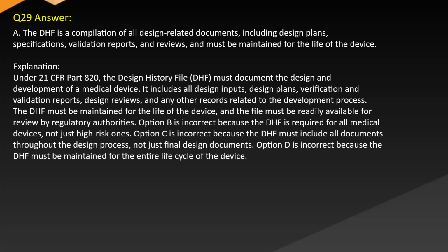Answer: A. The DHF is a compilation of all design-related documents, including design plans, specifications, validation reports, and reviews, and must be maintained for the life of the device. Explanation: under 21 CFR Part 820, the Design History File (DHF) must document the design and development of a medical device. It includes all design inputs, design plans, verification and validation reports, reviews, and any other records related to the development process. The DHF must be maintained for the life of the device, and the file must be readily available for review by regulatory authorities.